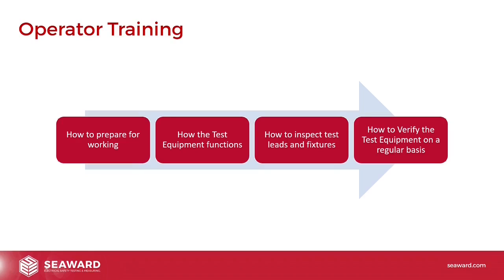So operator training, we need to cover kind of four areas. How to prepare for working, so kind of PPE, what they need to do to make sure that they're in a safe environment. We then need to talk about how the test equipment functions, so how to actually perform a test with the equipment, when it's dangerous, when it's safe, exactly how to use that equipment, the information the equipment gives the operator, that kind of thing. They need to know how to inspect test leads and fixtures, so they need to know how to make sure that for one instance their area is safe, but also how to visually check the equipment that they're testing. Both are really, really important. And how to verify the test equipment, how to verify it on a regular basis to make sure it's working and make sure it's actually correctly identifying fault conditions. So I'll go over all of these in detail.